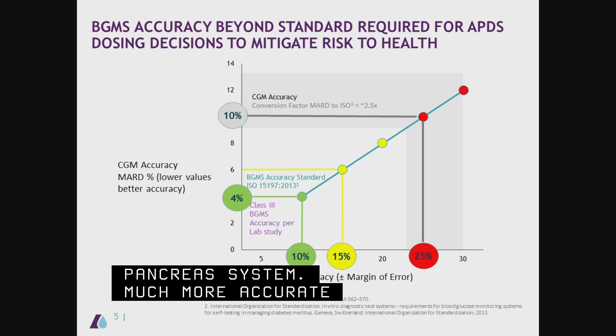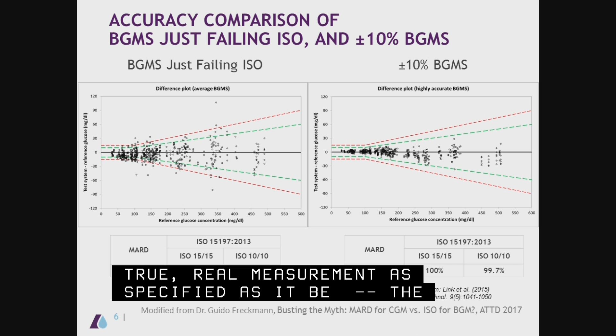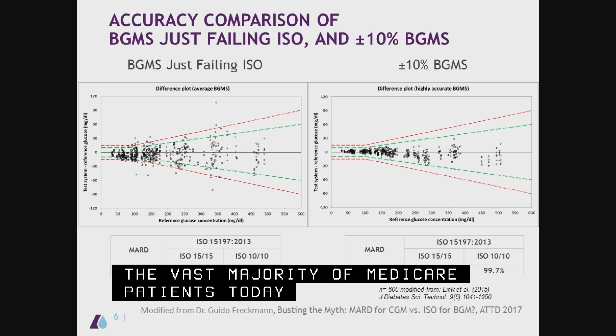This next slide just helps to visualize the differences in BGM accuracy we just talked about. We see the difference between a device that would fall just beyond the requirements for ISO, or that plus or minus 15%, and a plus or minus 10% rating. And as you can see, those results cluster much tighter to that true, real measurement as specified by the lab reference. You might ask why I'm showing the results of a meter that falls just short of the newly proposed FDA guidelines, and the reason is because many such systems exist on the market today because they're grandfathered. In fact, the vast majority of the strips purchased by Medicare patients today fall into that category.